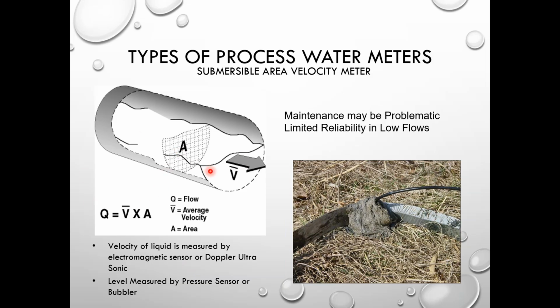The oldest type of flow meters is what we call submersible area velocity sensors, and they read velocity either with an electromagnetic velocity sensor or a Doppler transducer that shoots a signal up through the flow and picks up a velocity, right? And based upon the amount of pipe that it has, it's measuring level as well. The level measurement is typically done by a pressure transducer, but there are also bubblers. Bubblers have an air tube that comes down to the bottom of the pipe and pushes air out slowly, and based upon the back pressure to the controller, it's able to determine the level of liquid in your pipe.